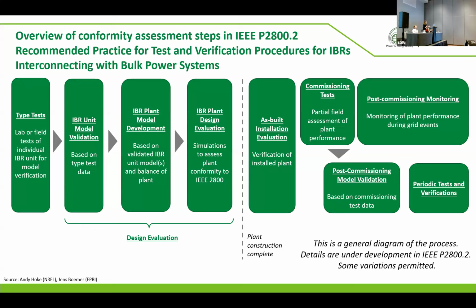And then this is where design evaluation is happening. So basically, as you're designing a plant, you are making sure that all components of the plant are conformant with 2800 requirements. So there is subgroup 3 that's working on all of these pieces of how to verify conformity during the design process. And then when the plant is constructed and it's all complete, there is as-built evaluation. So basically you're evaluating that whatever you verified in design evaluation is still the same. It didn't get changed. All the settings are being checked and models are being updated. And then there is commissioning and testing. So some of these things you can actually test in reality through physical tests. You do some model validation based just on this limited set of tests. And then there is post-commissioning monitoring.